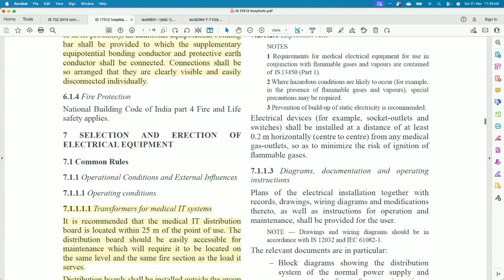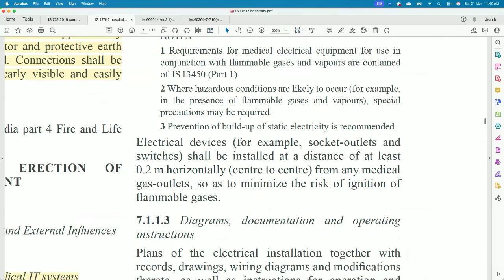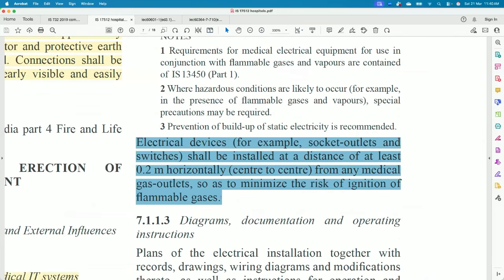One example which is a blatant violation in India, you can see I just highlighted: electrical devices, for example, socket outlets and switches, shall be installed at a distance of at least 0.2 meter horizontally, center to center, from any medical gas outlet so as to minimize the risk of ignition of flammable gases. So this is a very, very essential measure. I have a picture. I will show you later what happens.